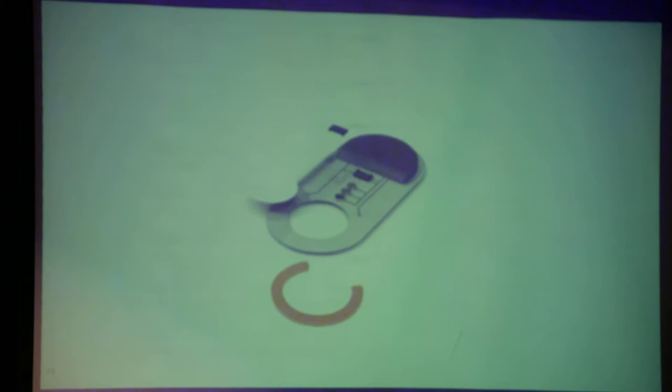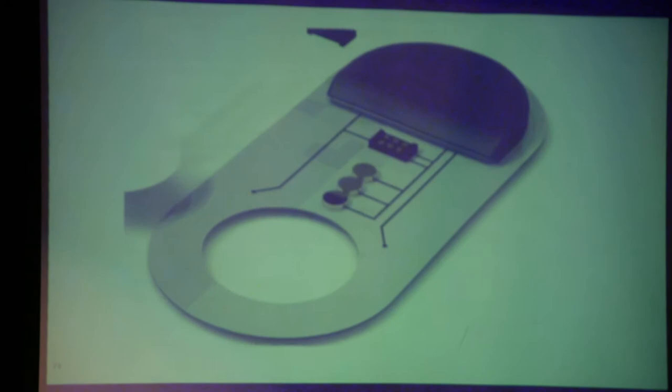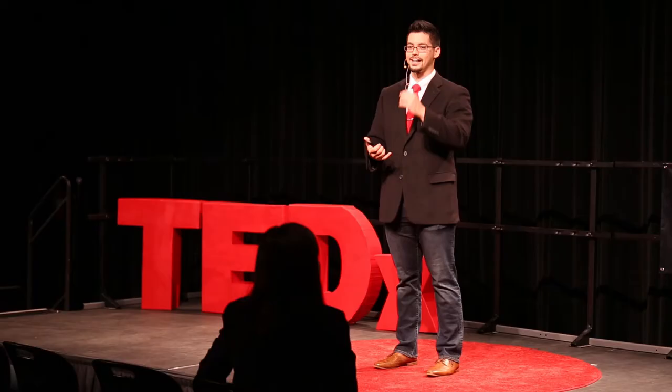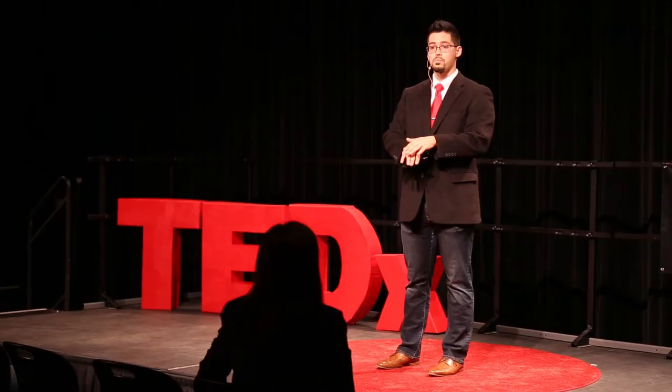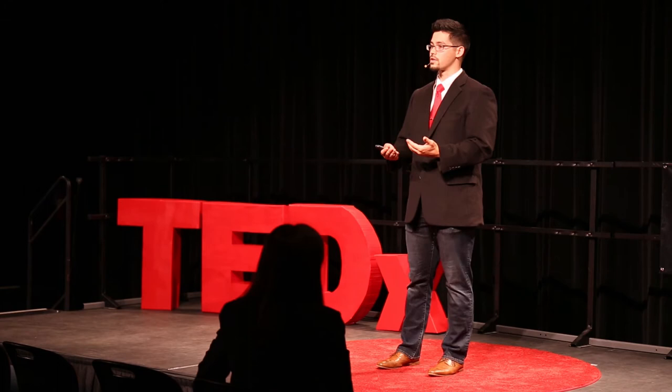And as we zoom in here, you'll see two different types of sensors. But the main two that we would be interested in are ion selective electrodes to measure sodium and potassium levels, and EABs, which are electrochemical aptamer-based sensors. And so aptamers are essentially, I like to consider them DNA magnets. I'm an electrical engineer in my background, so the biology world gets pretty confusing. But I consider them DNA magnets. One side attaches to an electrode, and as a fluid is present with, let's say, cortisol that this aptamer is designed for, then this biomarker will attach to your aptamer and fold over. And what happens is there's more electron exchange with your substrate, and your electronics can amplify that. So then, by however much is amplified, you can tell the concentration of different analytes or biomarkers in your fluid.